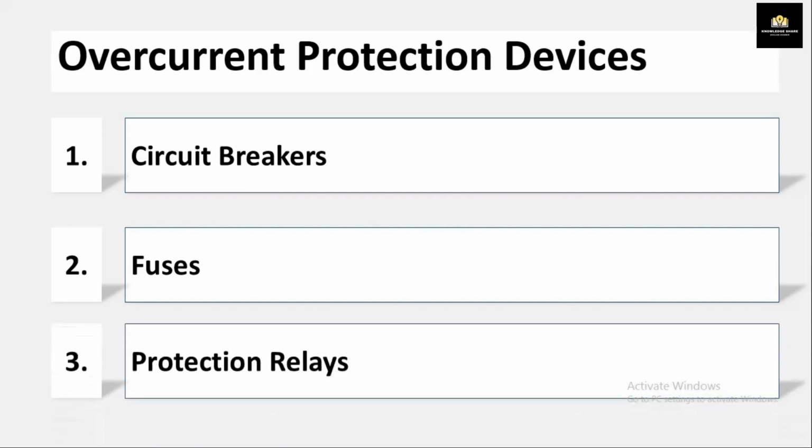Number 3. Overcurrent relays. The basic element in overcurrent protection is the overcurrent relay. The ANSI device number is 50 for an instantaneous overcurrent or a definite time overcurrent, and 51 for the inverse definite minimum time. When an overcurrent situation occurs, the protection devices act to disconnect the affected circuit from the power supply. The interruption prevents further damage to the equipment and eliminates the potential safety hazards. After the overcurrent issue is resolved, the circuit breaker can be reset and the power is restored.